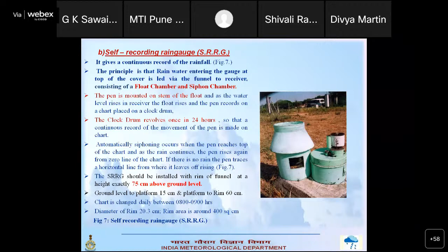So the internal of this self-recording rain gauge looks like this. This is the rotating drum, where we fix our recording paper, and this is the pen arrangement. It starts from 0 and goes up to the maximum of 10 millimeter. Once it reaches 10 millimeter, this is the siphon assembly. It releases water. Once the water is released, this pen again comes to the 0 level. Like that, it continuously records the rain.